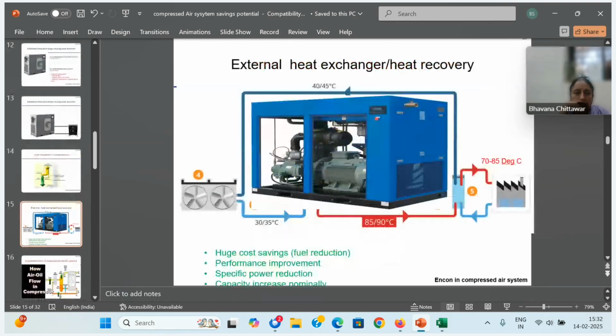So this is a typical thing I have done in some industries. I have put extra heat exchangers outside. In the left hand side, number 4, it dissipates the heat outside. It is spent heat. We cannot recover total heat. Whenever the heat recovery is not used, still there will be temperature, so we have to dissipate the heat. That radiator will be there. Right hand side, number 5, it's a plate heat exchanger. Hot oil at 90 or 95, it goes up to 95 sometimes, average 85 to 90 degrees will be circulated. Internal temperature will be 40 to 45. Again, it will be cooled further, it will be ambient plus 5 or 10 degrees, and it will go back to the system.